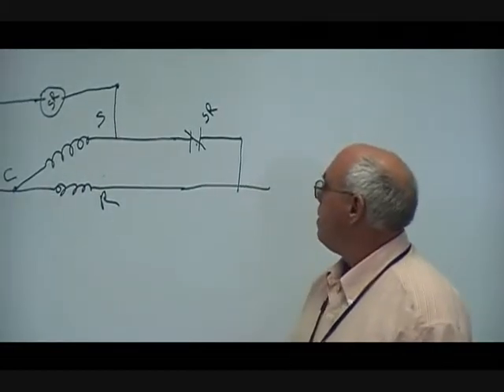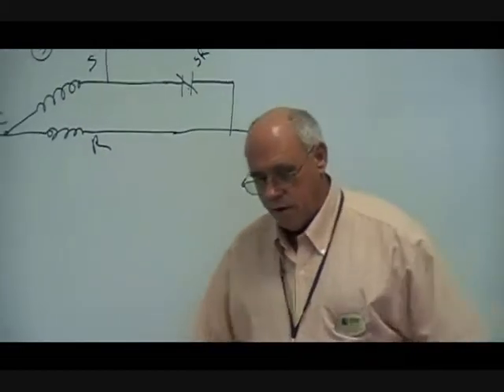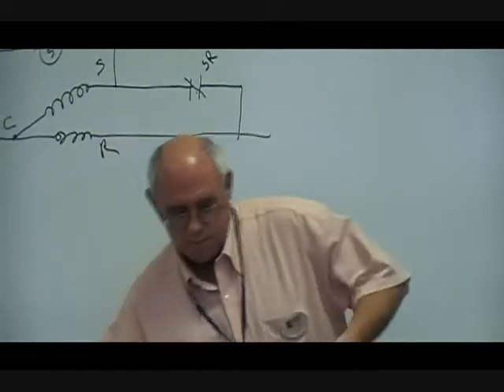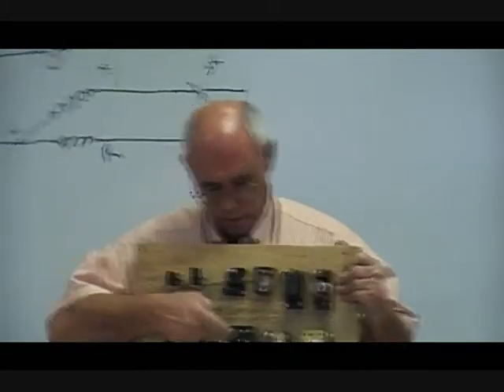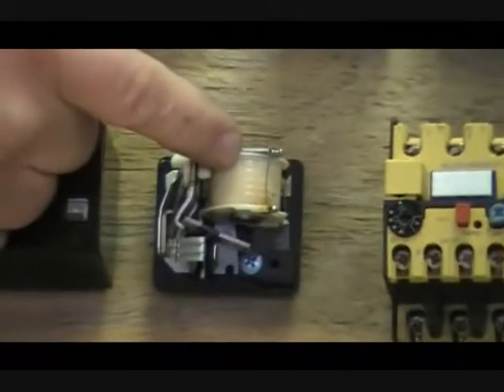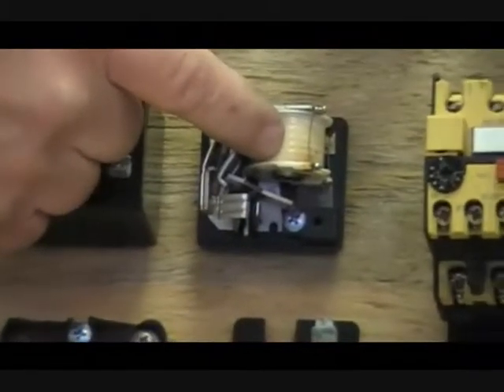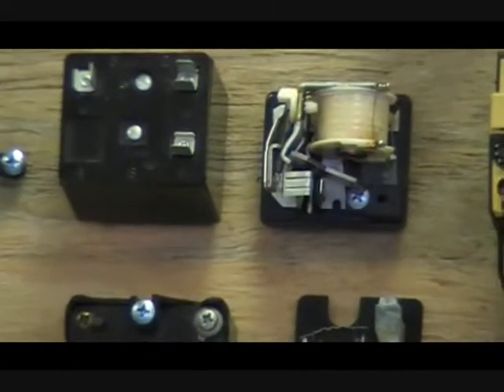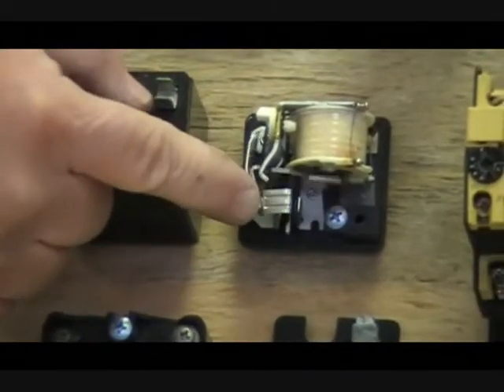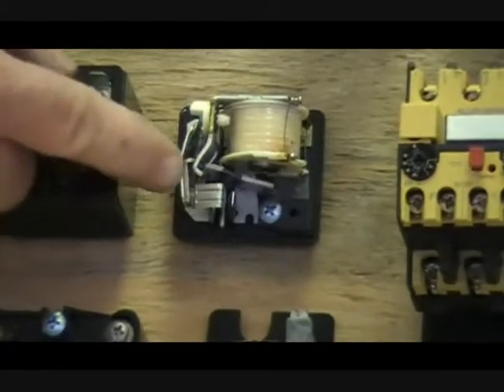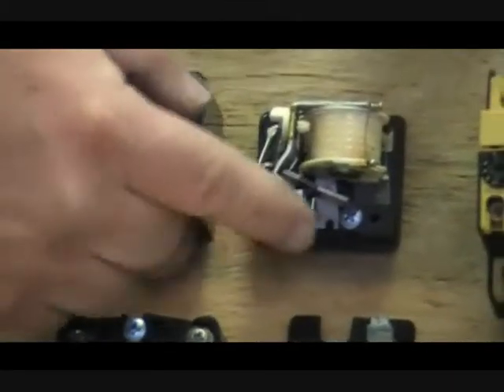You don't have the right component match, you take a chance of running this motor. That make sense? Well, what do they look like? That's the potential relay. Here's your coil on the potential relay. Notice the size of the wire on the coil. Much smaller. It's not measuring a lot of current. It's measuring voltage. What it does is move that set of contacts and opens them up when the voltage gets right.